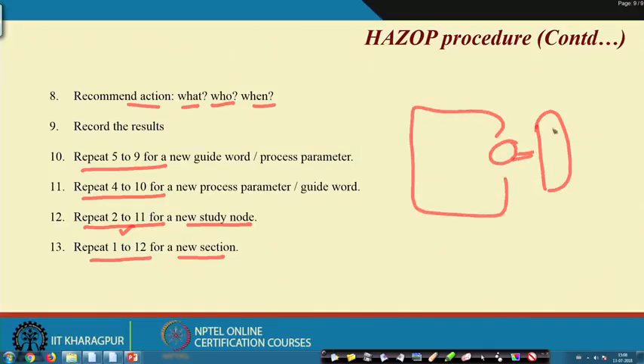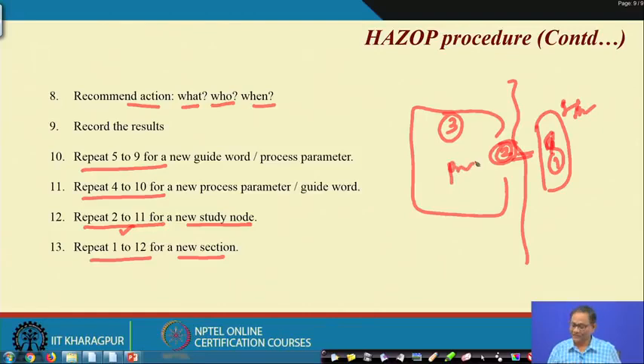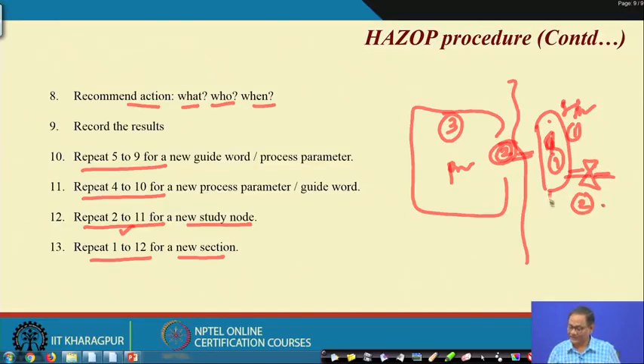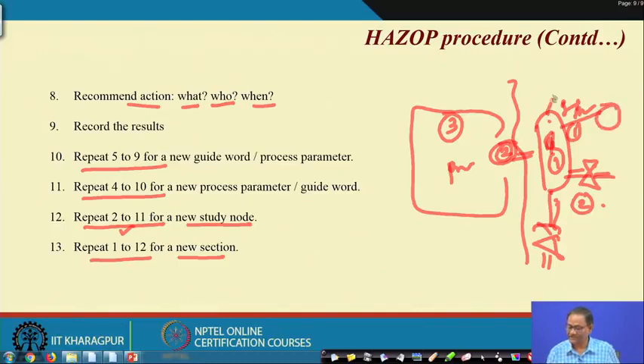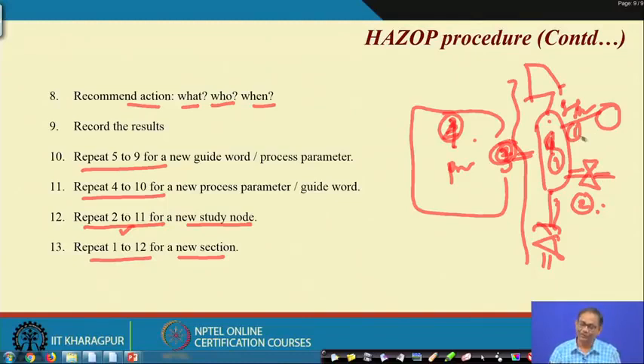Considering the pressure tank system as an example: tank is study node 1, pump is study node 2, and the rest is study node 3. You have considered two sections: one is storage, another is pumping. In the storage section you may consider the tank itself as one node and the relief valve as another node. In section 2 the pump is one node and the circuit is another node. You first divide into sections, then in every section find your nodes, and then for every node conduct the HAZOP study.